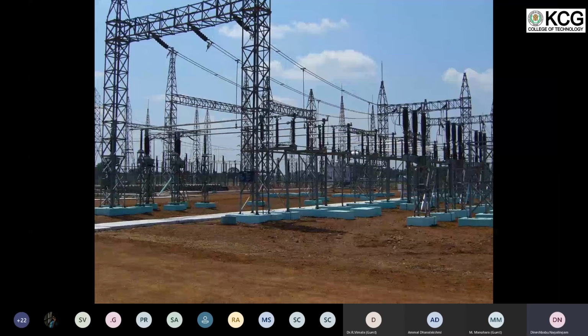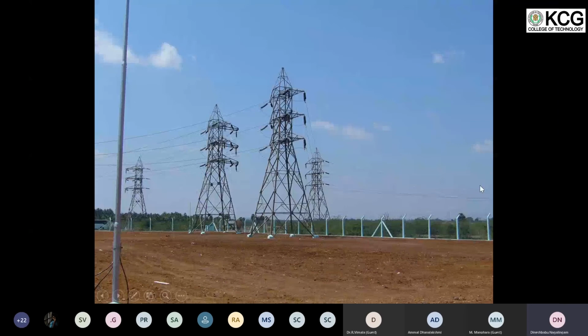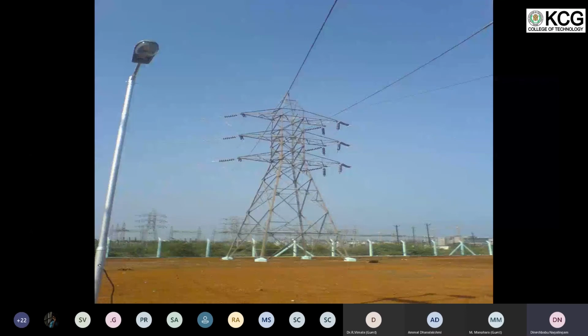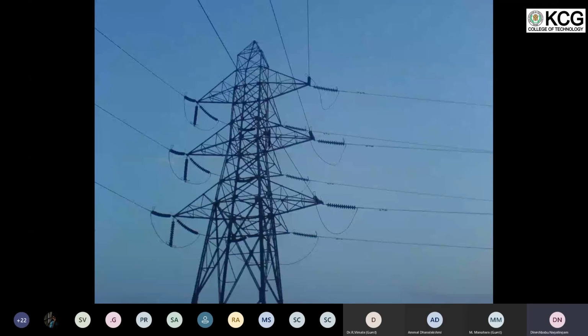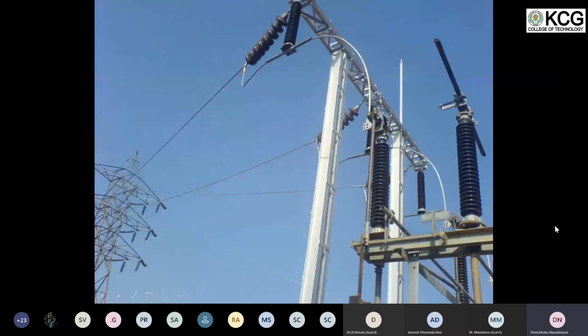This is how the transmission line tower enters. It's an L-shaped angle. So this is an acute angle. This is an obtuse angle. You can see in the acute angle, there are 2 insulators. The obtuse angle has a bigger insulator. This is to ensure that this loop doesn't touch the tower during wind loads. Whereas here the loop is very small, so it cannot go and touch. That is why we have 3 insulators here. So from the tower, the transmission line enters into the substation.